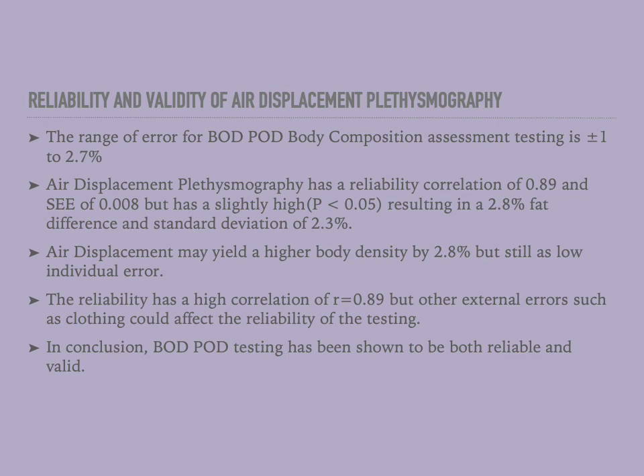Reliability and validity of air displacement plethysmography: the range of error for BODPOD body composition assessment testing ranges between plus or minus 1 to 2.7 percent, which is considered really low and good. The air displacement plethysmography has a high reliability correlation of 0.89 and SEE of 0.008. It has a slightly high p-value using 0.05, which results in a 2.8 percent fat difference and a standard deviation of 2.3 percent. The air displacement plethysmography may yield a higher body density by 2.8 percent, but still a low individual error.